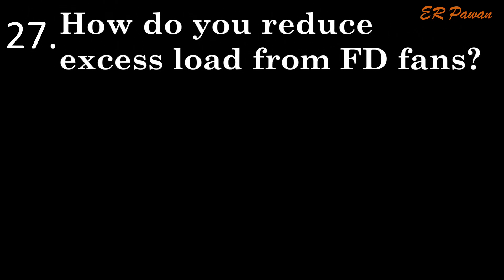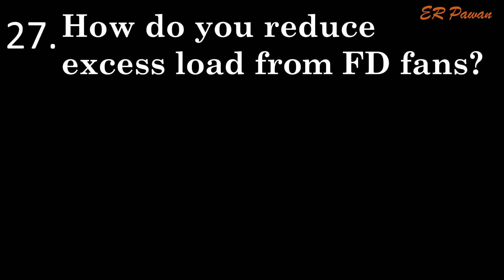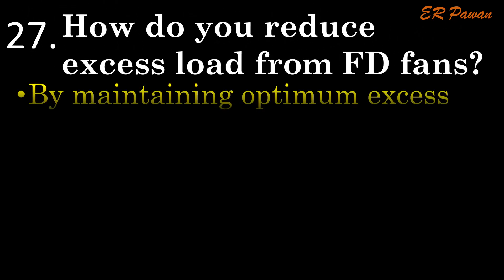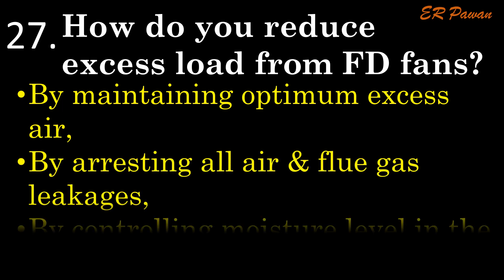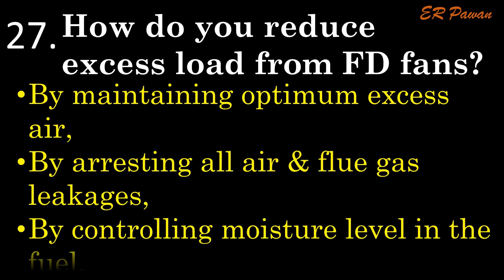Question 27: How do you reduce excess load from FD fans? By maintaining optimum excess air, by arresting all air and flue gas leakages, and by controlling moisture level in the fuel.